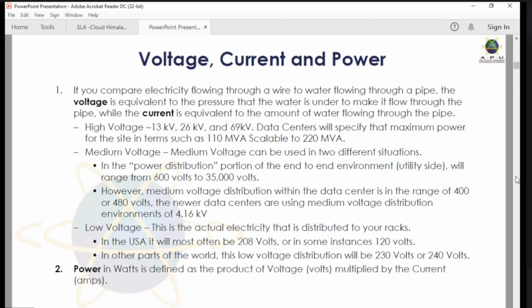480 volts. The new data centers are using medium voltage distribution environment at 4.16 kilovolt. Okay, low voltage, this is the actual electricity that is distributed to your rack. In the US, it's most often 208 volts or in some instances 120 volts. In other parts of the world, low voltage distribution will be 230 volts or 240 volts. Power in watts is defined as the product of voltage multiplied by the current. If you multiply voltage by current, it will give you the power. So 230 volts times 1 ampere is 230 watts.